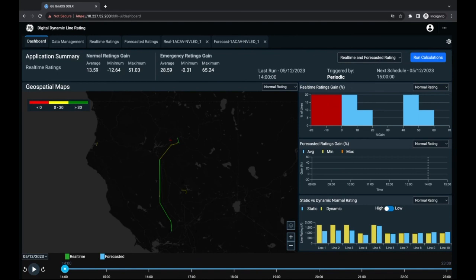This gives us the ability to run hourly updates, and the first point will always be a measured point, as we get from the weather data provider. These are the weather measurement stations on the ground, close to where we live, close to our power lines, and so on. The forecast rating is also going to be available to comply with the FERC Order, and we'll get into those. So, real simple. You can get the ratings, you can get the gain, and this is the capacity that you're currently getting out of your current infrastructure as we operate safely.